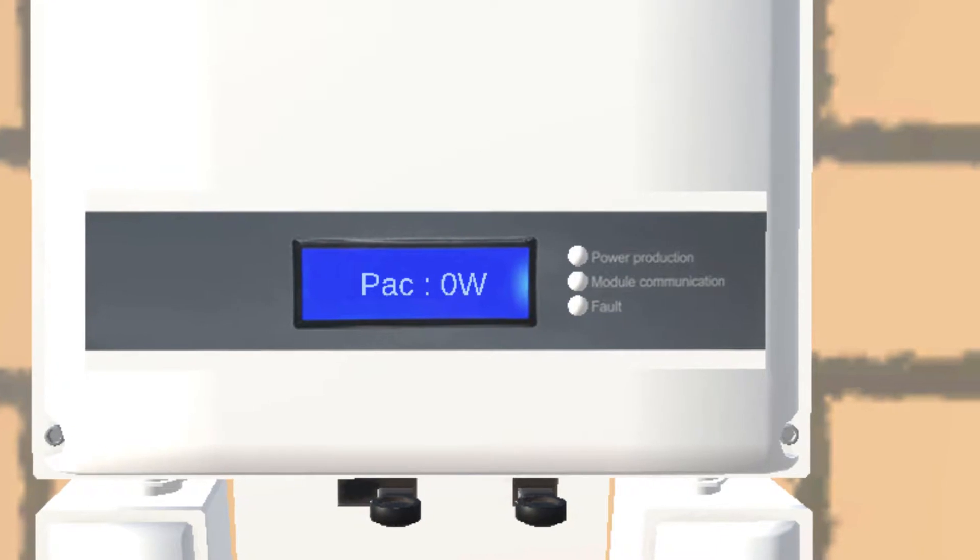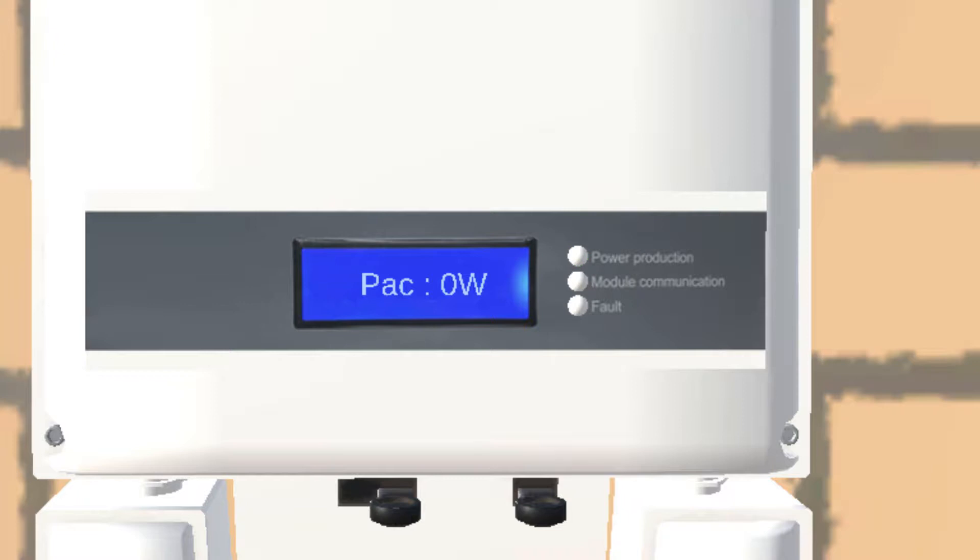The first thing that you want to do is follow the question which says which operating condition is indicated by the inverter lights? If we look over at the inverter display we'll either see a display in the blue with some information or one of the LED lights on the inverter indicating something. In this case it says PAC power AC output is zero and we have a blinking green power production light.